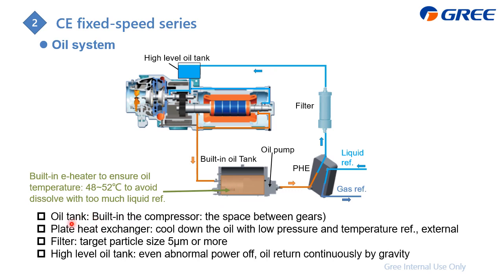So for this one, first is the oil tank, which is this one. It is built inside the compressor, just between the gears, between this part. And the next is the plate heat exchanger to cool down the oil by the refrigerant. This part is external. And the next is this filter. The target is to stop or filter particles of size more than 5 μm.